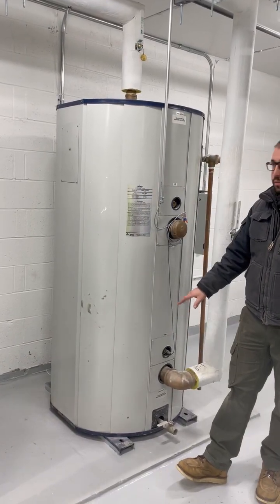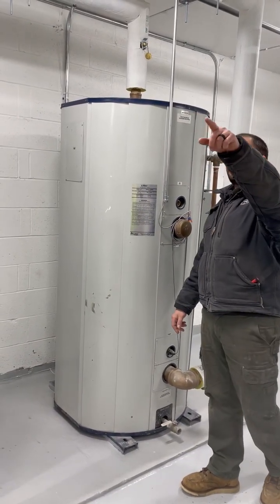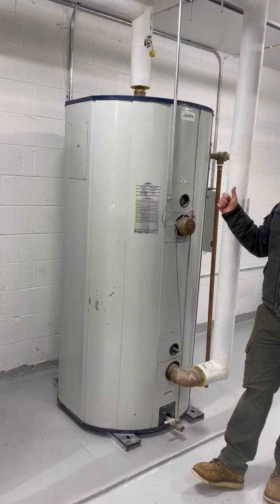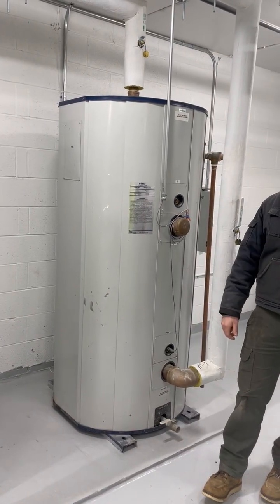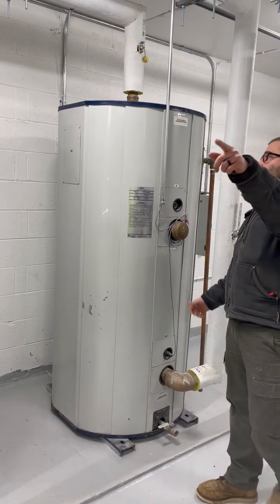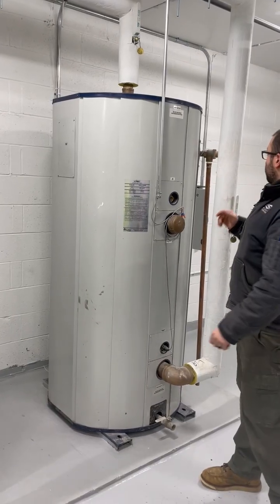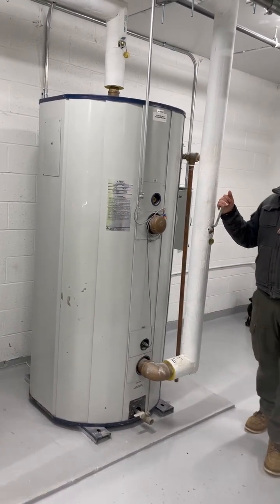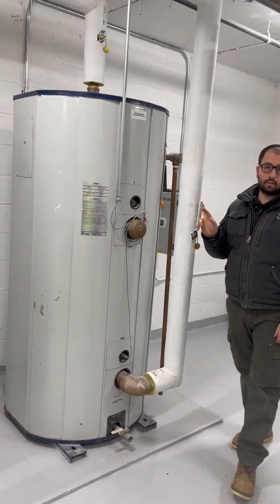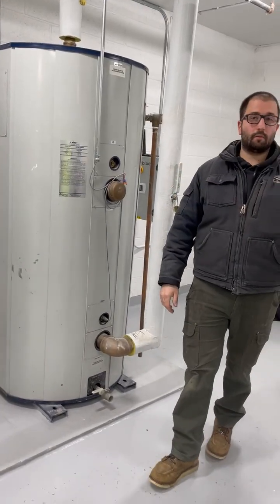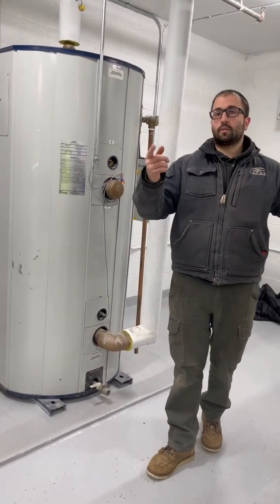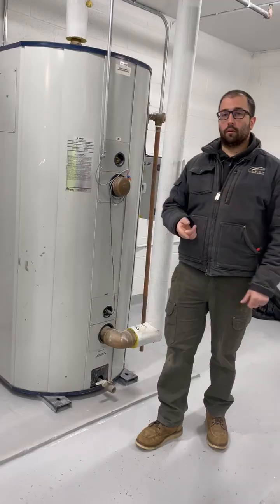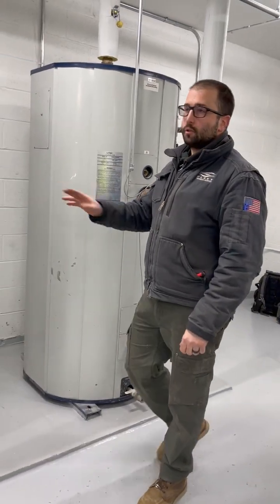The reason is when we're feeding into that tank the hot water, we're pulling off this tank for the cold water into our skids. So we're feeding over there, pulling from here. It's very important that none of these valves are closed. When you close these valves, you're not only stopping flow to these, you're also stopping domestic hot water flow out to your building. It should never be off.